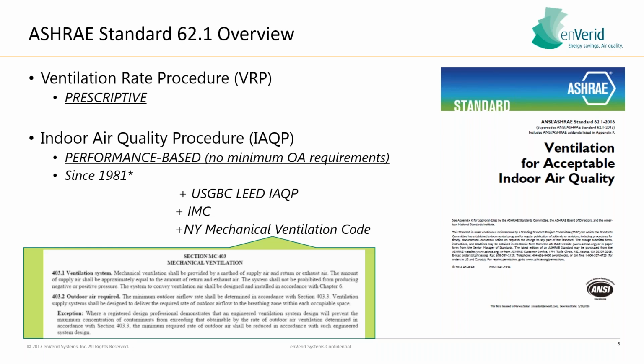The other, which is until recently lesser known, is the indoor air quality procedure, where you deploy indoor air cleaning, which enables you to reduce the amount of outside air required. It's essentially a substitute for outside air by removing all the contaminants that are emitted within the space. ASHRAE 62.1 is referenced in Ontario Building Code, also referenced in the International Mechanical Code 403. So both of these sections apply equally within code, so that you don't need to apply for variances if you're using indoor air cleaning in the indoor air quality procedure as opposed to ventilation rate.